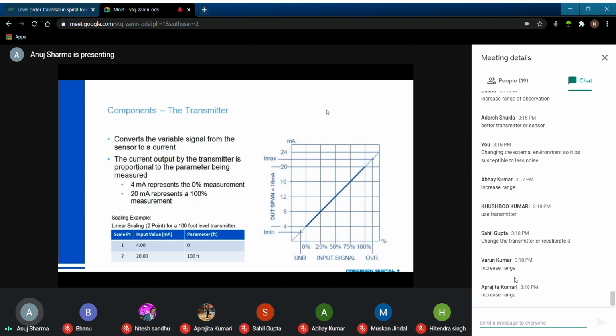The 4 to 20 milliamp signal doesn't stop exactly at 4 and 20 milliamps. Most devices, most transmitters and receivers, can handle an over and under of some percentage, usually in the ballpark of, let's say, 5% or maybe half a milliamp. The purpose is that these things tend not to be precise. You may get a 0 to 100 foot level transmitter, like the scaling example given here, but based on where your pumps are going to have to go at the bottom of the tank and where you calibrate the 0, there's a chance that you're going to go under the 0, that is 4 milliamps. And similarly, you could end up going over the limit you have set up to be your 20 milliamps.